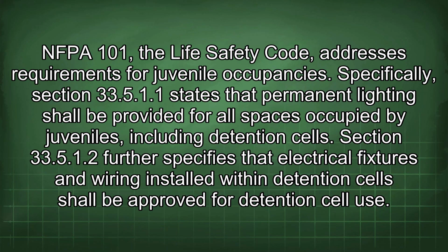NFPA 101, the Life Safety Code, addresses requirements for juvenile occupancies. Specifically, Section 33.5.1.1 states that permanent lighting shall be provided for all spaces occupied by juveniles, including detention cells. Section 33.5.1.2 further specifies that electrical fixtures and wiring installed within detention cells shall be approved for detention cell use.